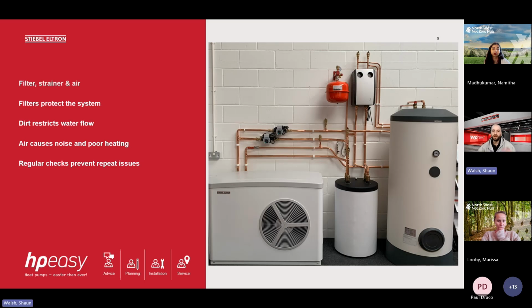Okay. And all these things, they'll generally lead to loss of comfort and complaints before they'll lead to an actual breakdown. The heat pump is never typically the first thing to break. 95% of the issues are caused on the system side of it. Okay. And if we don't check these filters and strainers and diverter valves and things like that, the issues will just keep reoccurring. So it's important that we check those all of the time. Okay.